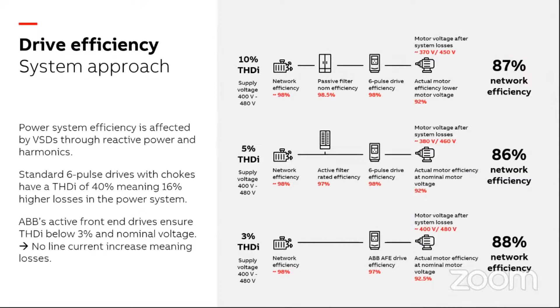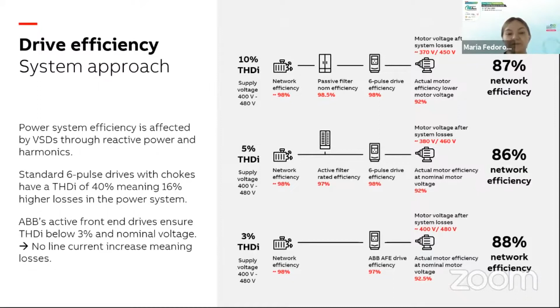In the very last system, shown at the bottom of the page, the initial drive efficiency is not that high, but as it is a prominent active front-end drive technology, it's able to significantly improve the power quality of the network it's connected to. Therefore the total system efficiency is higher than in the first case, where we had a very efficient drive but did not consider that the system would require extra solutions to improve its power quality. So when selecting drives for a system, be wise and look at what kind of effect the drives bring in terms of power quality.